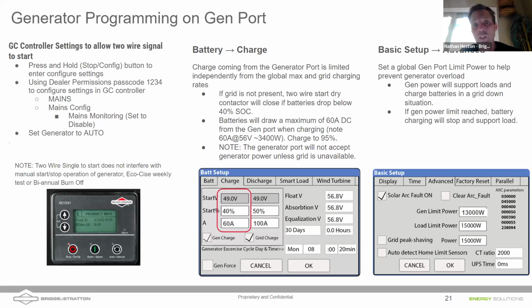However, in a grid down situation, if we look at that setting there in the left column, if the battery percentage goes below 40%, what will then happen is it will send a two-wire signal to start up the generator, and once it qualifies that generator source, it will charge the batteries at up to 60 amps DC. So that's 60 amps at 50 volts approximately. So we're looking at about 3,000 watts of charging. You can increase that number for our batteries all the way up to 195 amps if you've got a 3-stack of our batteries, up to the 275 amp limit on the Sol-Ark. That's amps DC, keep that in mind.